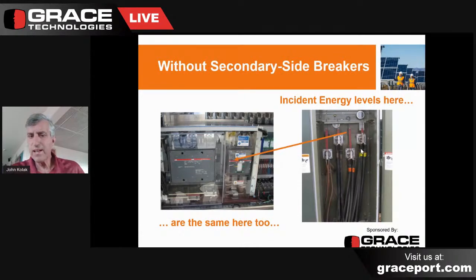Now, this is an important concept for us to consider as engineers as well, and also as workers. What you have on the secondary side of the transformer, the low voltage side, you have that same thing coming up. In this case, it's bottom fed into that particular breaker that you see there. So many times workers would say, well, I would never take voltage readings, for example, right in a pad mount transformer because of the explosive potential, yet they would go into the inverter skid itself and take voltage readings on that breaker there.